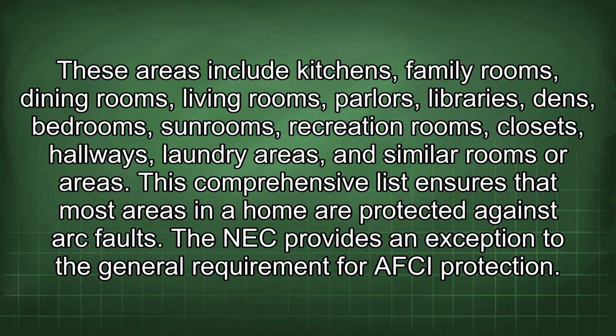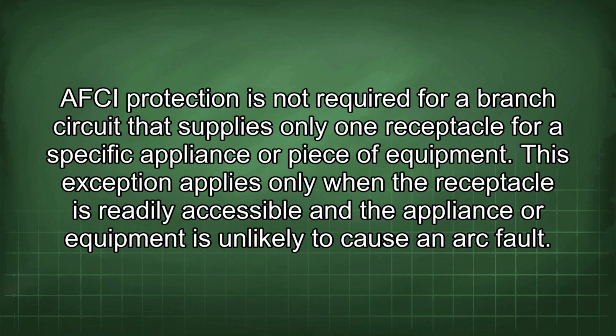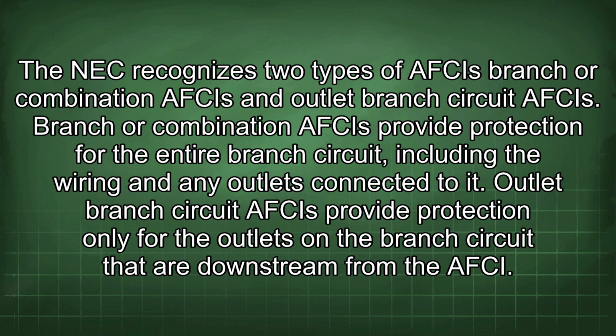The NEC provides an exception to the general requirement for AFCI protection. AFCI protection is not required for a branch circuit that supplies only one receptacle for a specific appliance or piece of equipment. This exception applies only when the receptacle is readily accessible and the appliance or equipment is unlikely to cause an arc fault. The NEC recognizes two types of AFCIs: branch or combination AFCIs and outlet branch circuit AFCIs. Branch or combination AFCIs provide protection for the entire branch circuit, including the wiring and any outlets connected to it. Outlet branch circuit AFCIs provide protection only for the outlets on the branch circuit that are downstream from the AFCI.